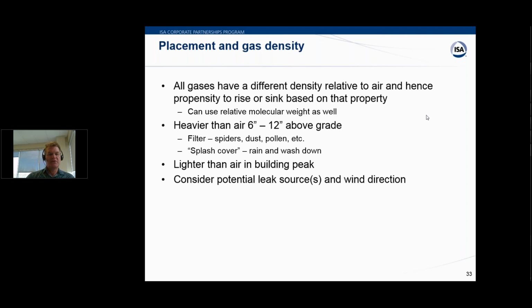Generally, if it's lighter than air, which most LEL detectors are, they'd be higher up, either above the point source or near the peak of the building, which then means you'd have to run your calibration gas up there to calibrate them. And then the other thing we always look at is where would it leak? So flanges, that type of thing, and wind direction, right? So if your wind predominantly comes from the north, then you're going to want to place your gas detector slightly south of the leak point.